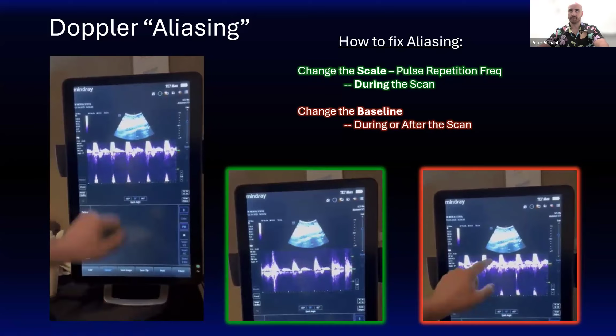And you have to do this while the machine is shooting sound waves out, that is the pearl. I can't tell you how many times people try to do this by just zooming in and out, but it has to be while the machine is shooting sound waves out. The other way you can do this is by changing the baseline. By simply dragging that green line down, sometimes you can address this aliasing issue. And this can be done either while the exam's happening or afterwards for the baseline aspect.